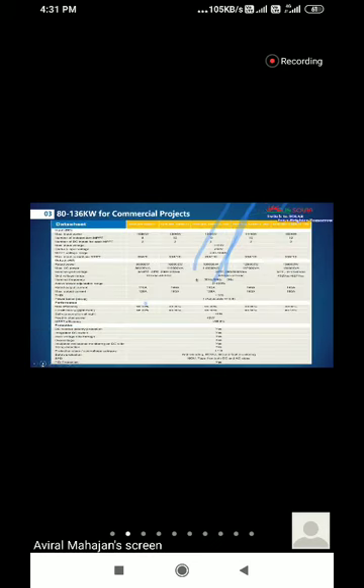This is the datasheet of the 80 to 136 kW inverter — the best solution for commercial projects. Features include Type 2 SPD for both AC and DC sides, temperature and humidity detection, 10 MPPT trackers with 40% overload capacity, and operation at full load up to 50°C. It features a second-generation software platform, 24-hour monitoring, and IP65/IP66 protection. These inverters will be available around September or October in the Indian market.